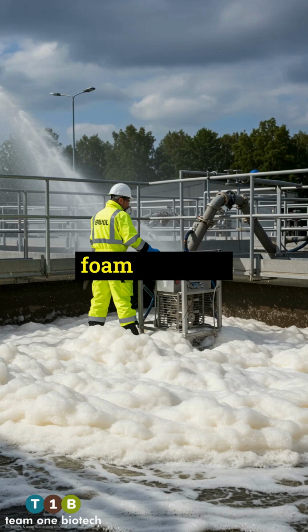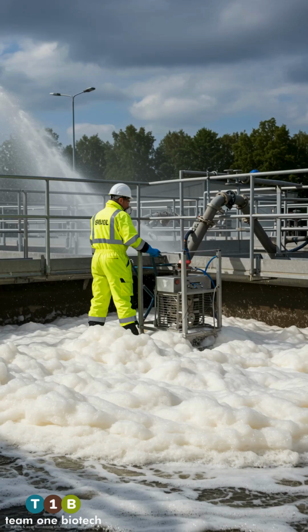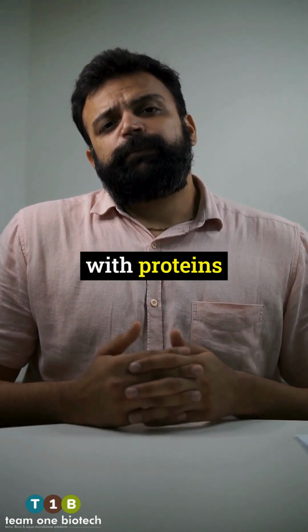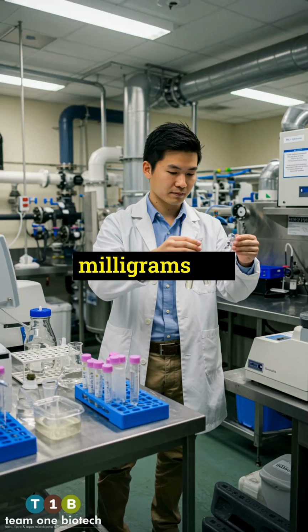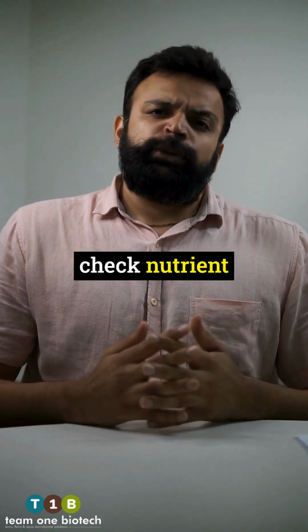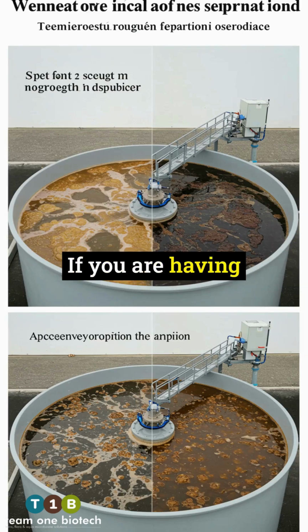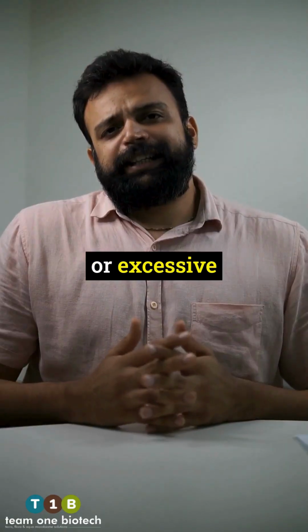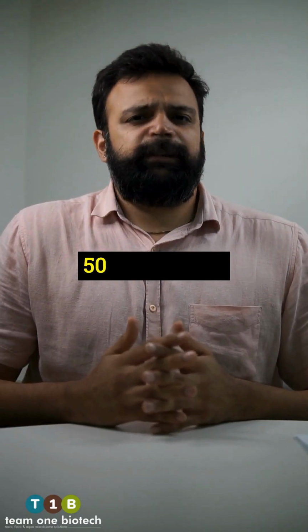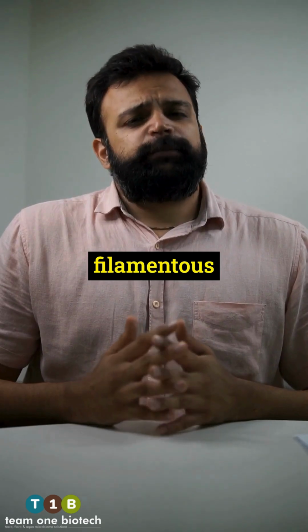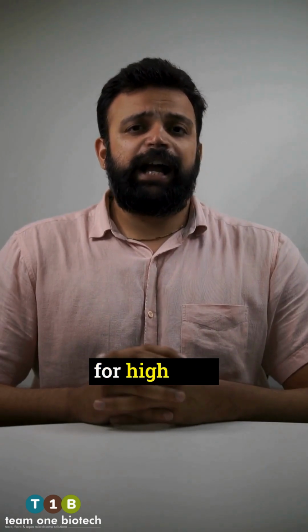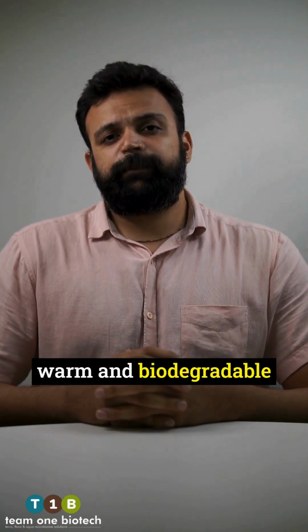Use mechanical foam breakers or surface sprays. Avoid overloading of protein. Limit the discharge with proteins to less than 300 mg per liter protein equivalent. Also, check nutrient balance and FOG. Imbalance impacts. If you are having low nitrogen or phosphorus or excess FOG more than 50 milligrams per liter, filamentous bacteria grow. Anaerobic systems are best suited for high COD, warm and biodegradable effluents.